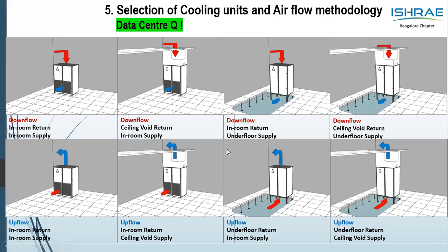In the ISHRAE norms case study, we found the racks have servers, and cold air, being high in density, will pick up the heat, and hot air, being low in density, would naturally go back to the unit. Thereby, the right option would be the first four, because all these are bottom throw. This is a frontal throw, so this is also okay to be used in a server room.